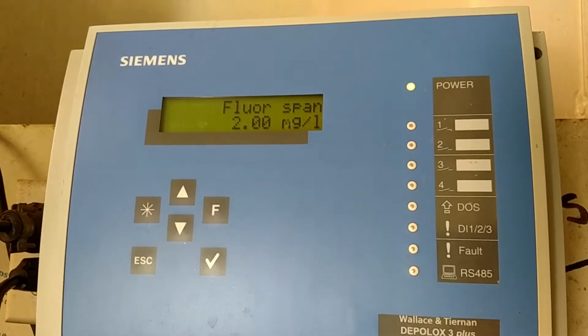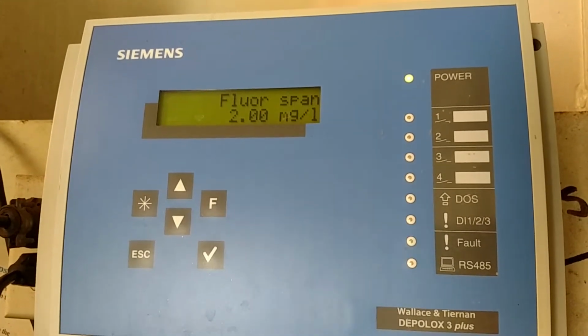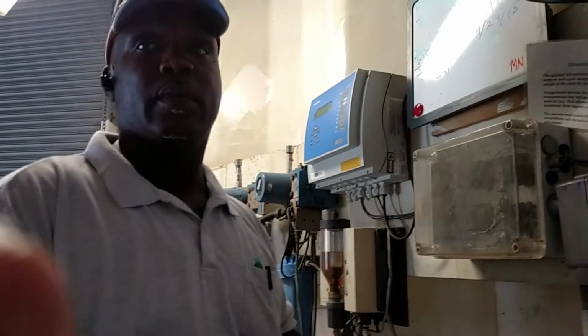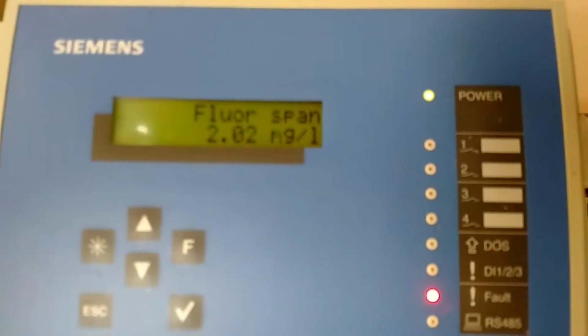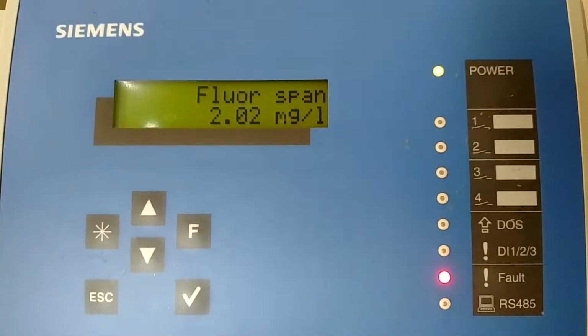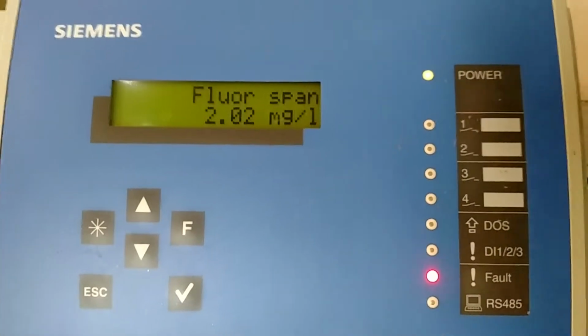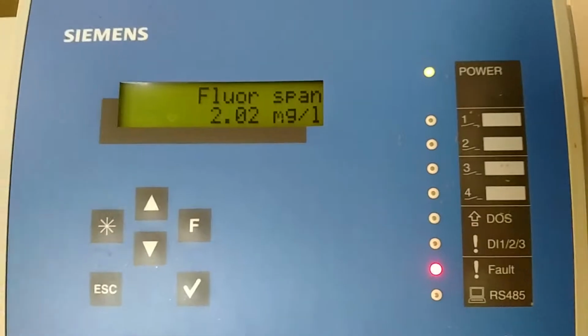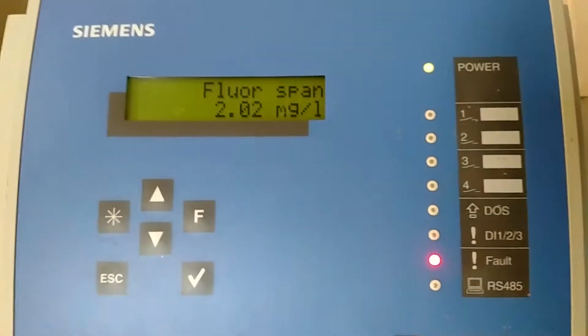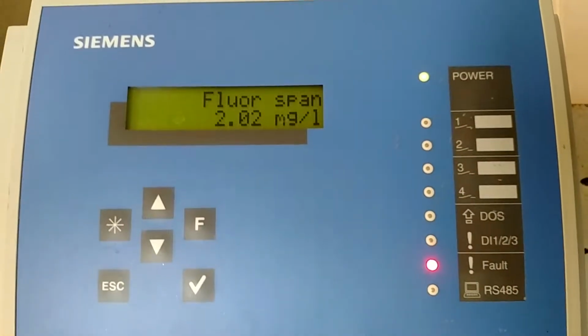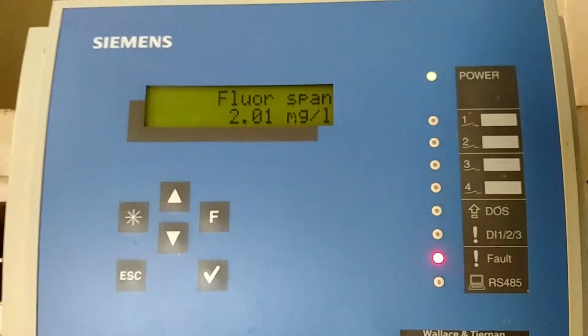Give it a few seconds. And what I have to do is I'm going to record that reading as well as after I calibrate it, what did it read. Okay. So it basically is reading a 2.01, 2.02, and it's going to continue to keep drifting up. So I would say probably like a 30-second time frame just to go ahead and just record it, because if you just waited for like a minute, you're going to be here for a while. Oh, okay.